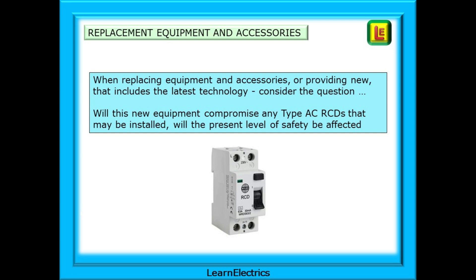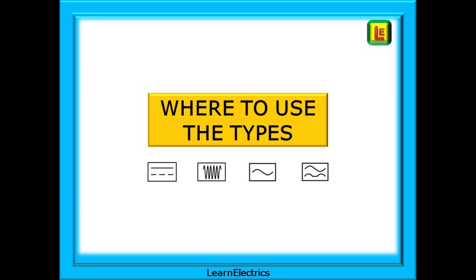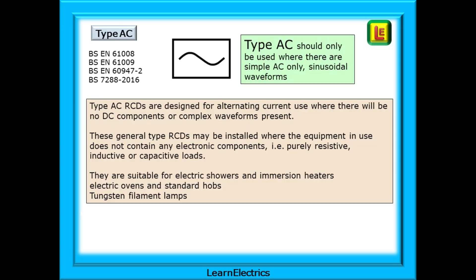Consider the questions: will new equipment compromise any type AC RCDs that may be installed? Will the present level of safety for the user be affected? Type AC are the general purpose RCDs we have installed for many years — the basic RCD, if you like. They should only be used where there are simple AC-only sinusoidal waveforms.